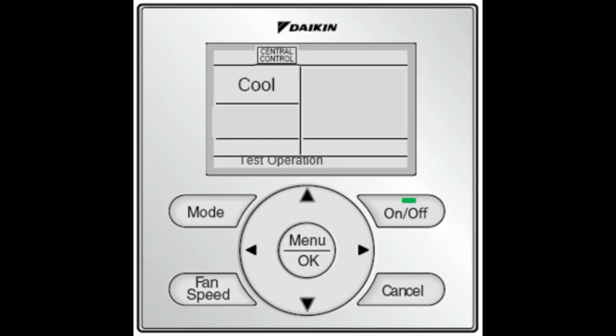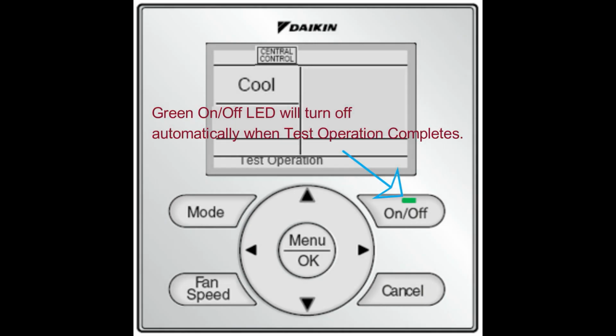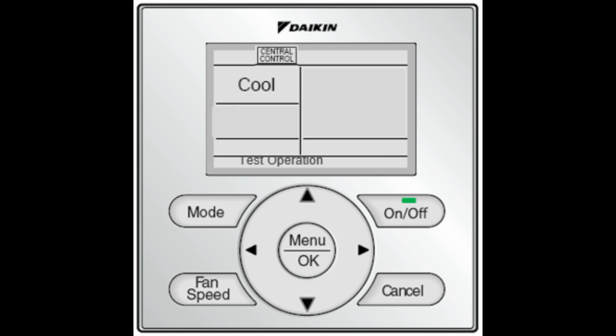Also, during the test, your thermostats will all be locked out and will display test on each screen. Once test operation has completed, you may now operate the equipment normally from the thermostats and or from the ITM central controller. Before you let the end users loose though, it's important to note to connect a Daikin service checker to the equipment and monitor the operation of each unit.